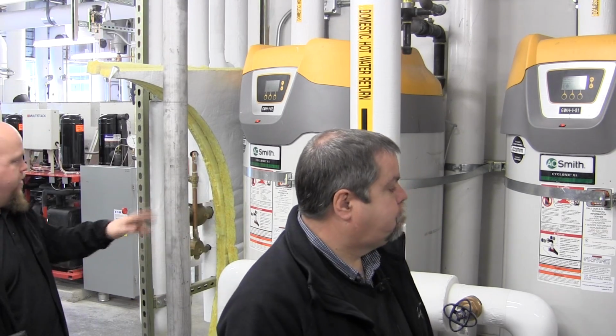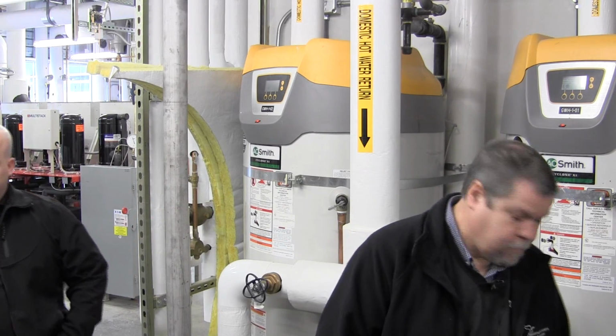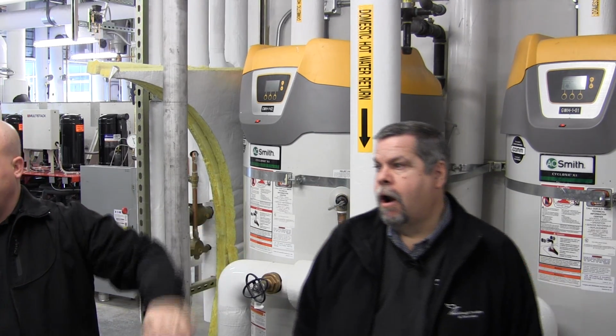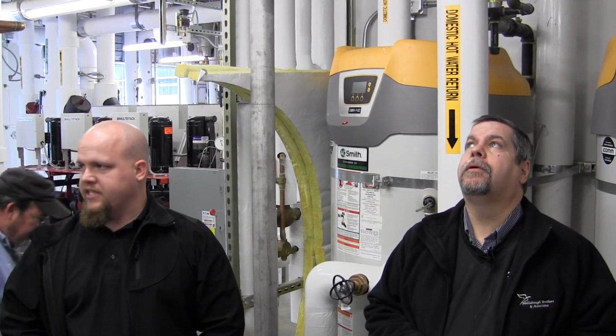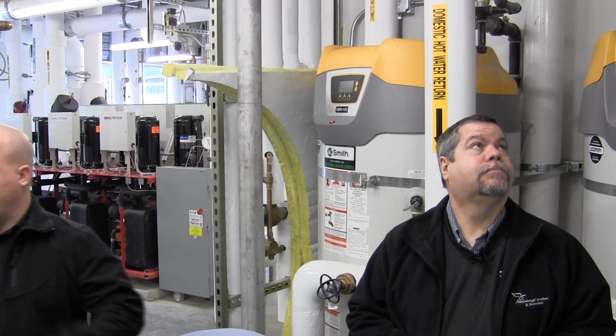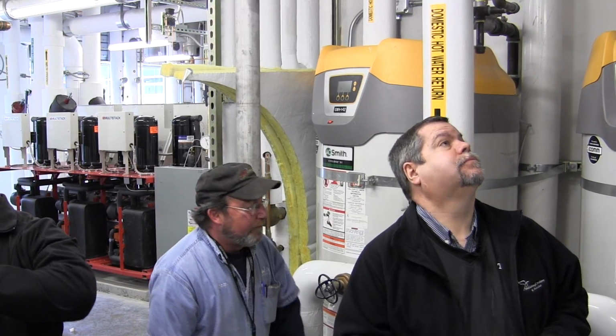They're both domestic. This is for the domestic hot water, gas hot water. That's for the solar. And then they mix. Eventually, the solar feeds into the domestic, and then they both go through the mixing valve. It goes right into the domestic tank. The solar basically preheats the gas water heating system. The point of the solar is to make it so these don't have to run. That's how you save. So it's a thermostat that controls it. On the solar, it has some sensors tied into the DDC on the pumps. So when there's solar available, it's going to circulate, run it through the heat exchanger.